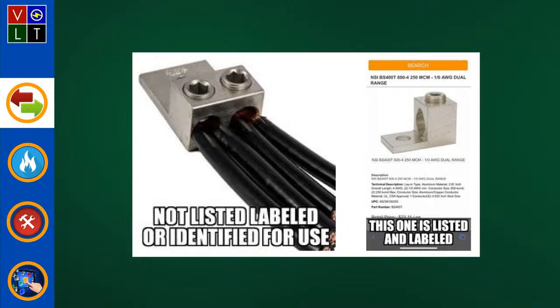I could see where David's coming from, that if you have say a 2-aught on one and then you tried a number 6, they wouldn't really seat that good even if they are listed for paralleled conductors. Typically what I've seen, those conductors are the same size, but in that condition we had out in the gas and oil patch, that was the only way we had to do it.